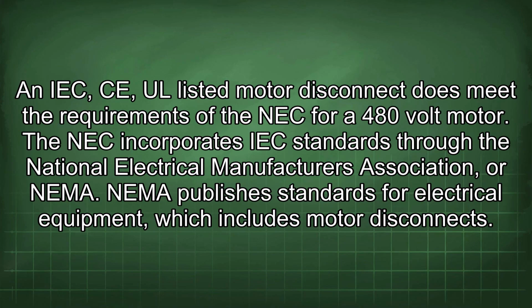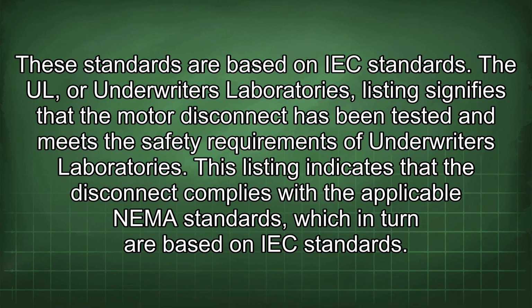An IEC UL listed motor disconnect does meet the requirements of the NEC for a 480-volt motor. The NEC incorporates IEC standards through the National Electrical Manufacturers Association, or NEMA. NEMA publishes standards for electrical equipment, which includes motor disconnects. These standards are based on IEC standards.